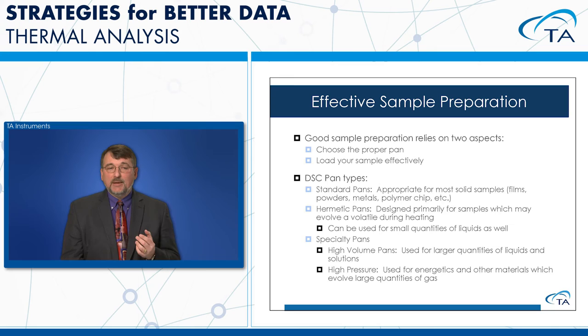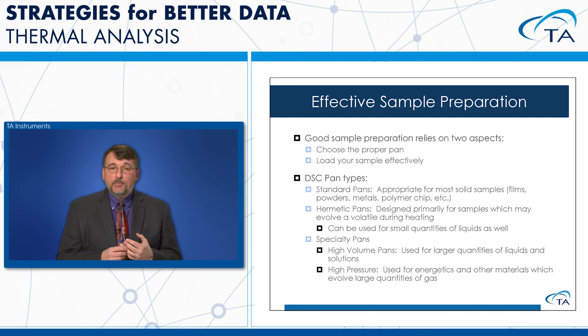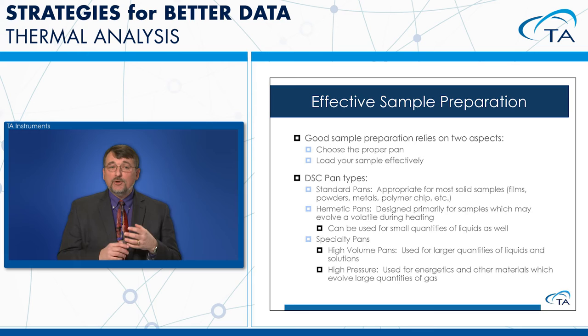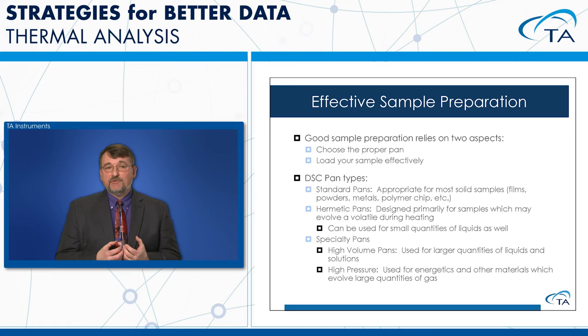There are multiple DSC pan types, and the right pan depends on your sample. Standard pans are appropriate for most solid samples — films, powders, metals, polymer slices. Hermetic pans are good for samples with volatiles you want to retain, and for small quantities of liquid. Specialty high-volume pans accommodate larger samples and maintain a hermetic seal. High-pressure pans are used when the sample generates large quantities of gas and high pressures during volatilization.